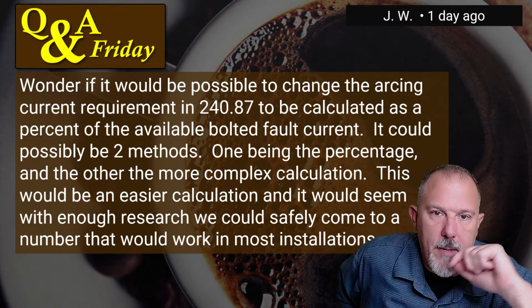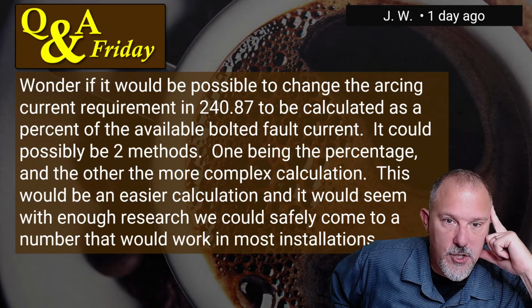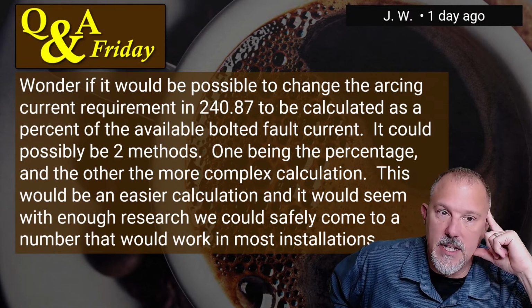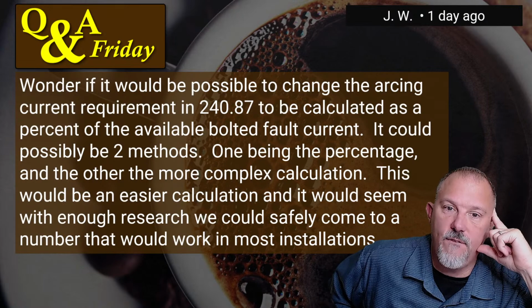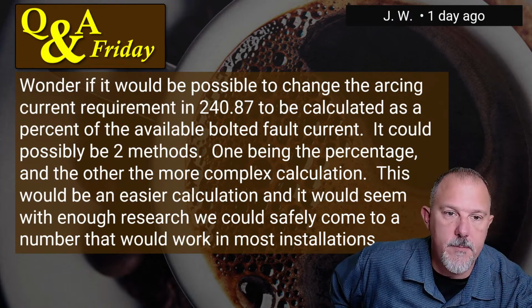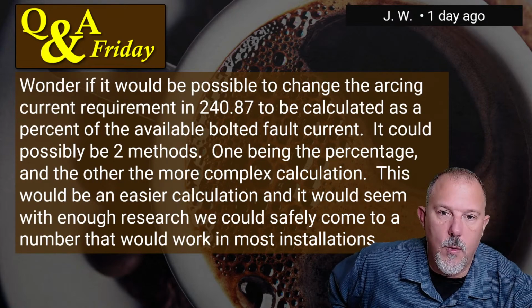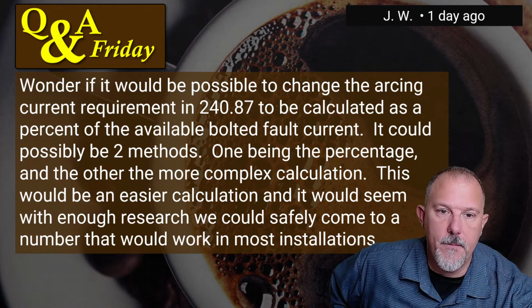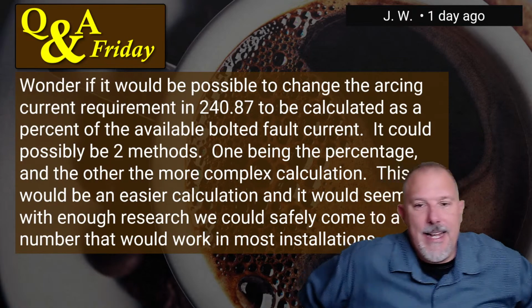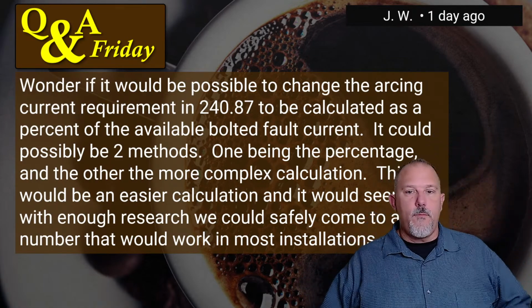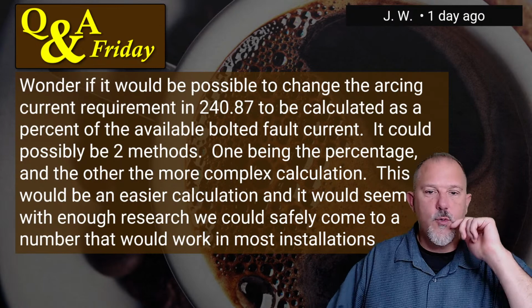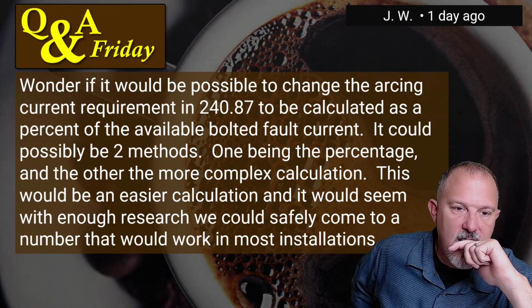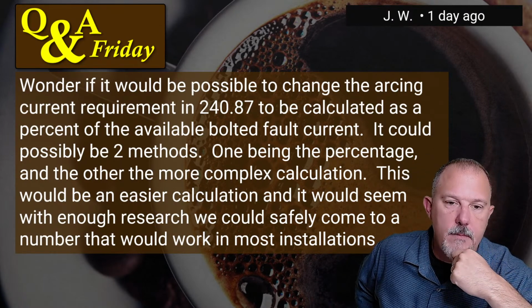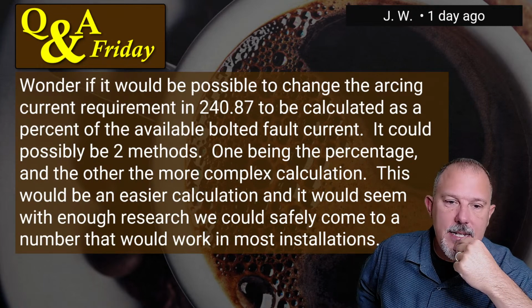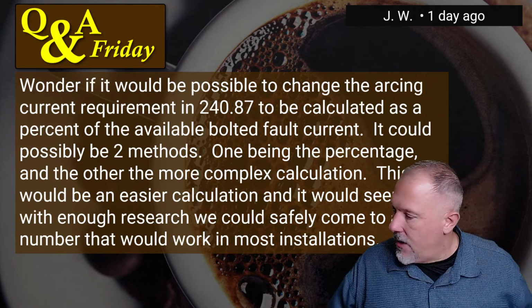I wonder if it would be possible to change the arcing current requirement in 240.87 to be calculated as a percent of the available bolted fault current. It could possibly be two methods, one being the percentage and the other the more complex calculation. This would be an easier calculation, and it would seem, with enough research, we could safely come to a number that would work in most installations. All right, how would I answer this one?